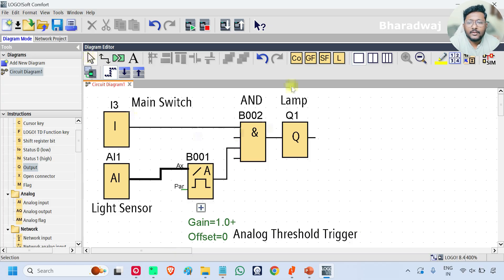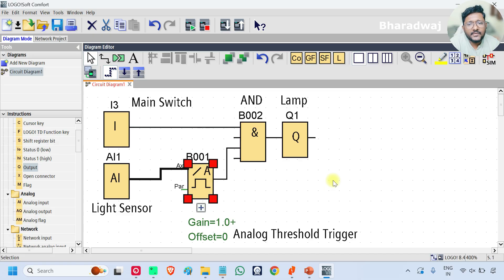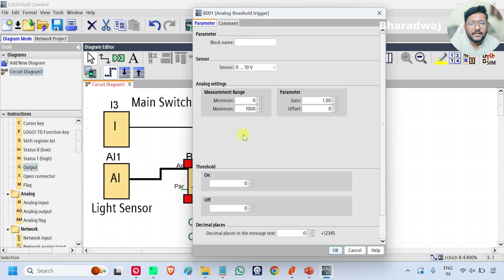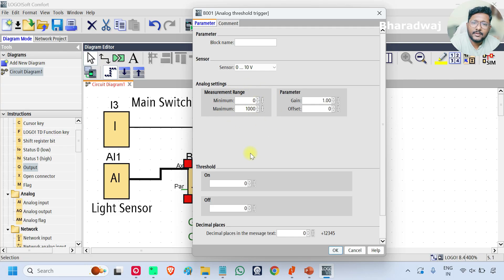Now, if you see, this is the main logic of our complete program. One important thing we have to do is set a defined range so that the lamp will turn on or turn off based on that range. That range we have to set in the analog threshold trigger. Here we define one value and based on that we generate one digital output which we use in the AND block. Go to properties. The default range is 0 to 1000 in LOGO PLC. The default range will always change based on your PLC type — remember that. I am using the same 0 to 1000 default range. You can change this range as per your sensor using gain and offset.